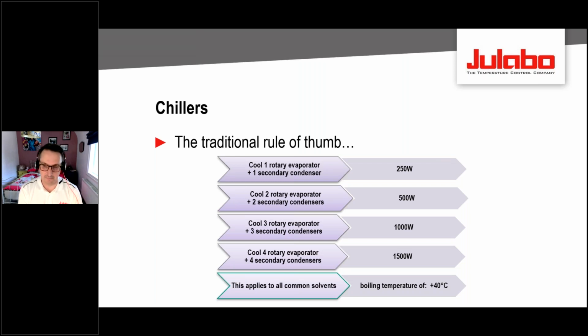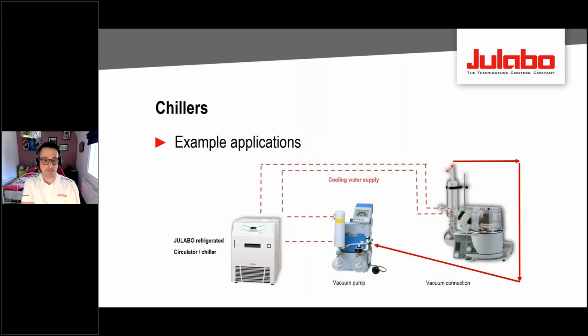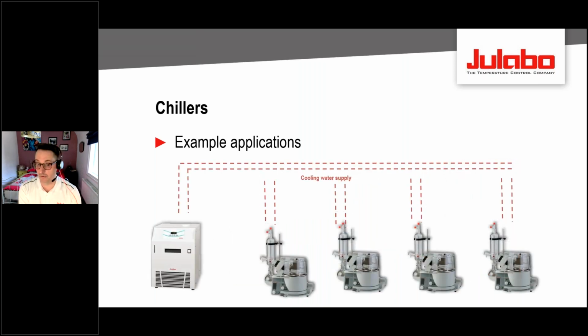If you've got larger rotary evaporators, or want to put 3 or 4 condensers into one series, you're going to need more cooling power. But you're also going to need higher pumping capacity, because this basic chiller with a pump can quite happily do 2 devices, and probably 4. But if you go to 5 or 6, you need to start thinking about pump capacity and flow rate through the system.